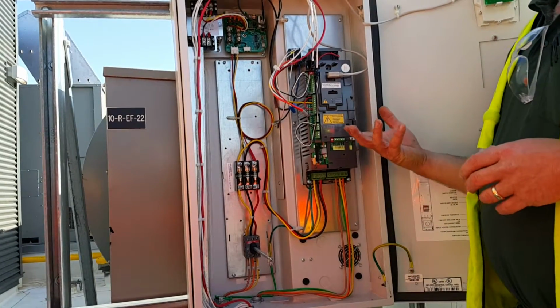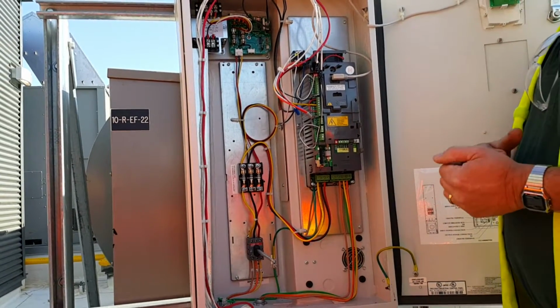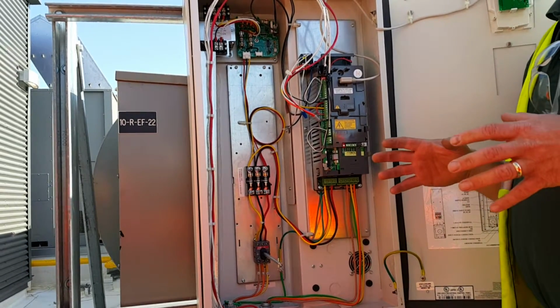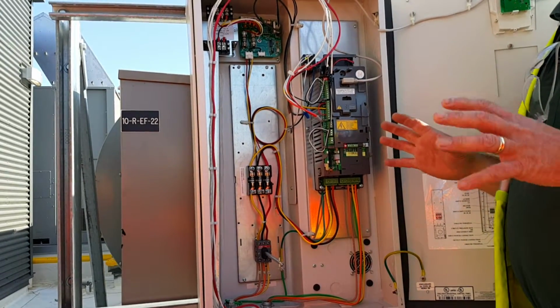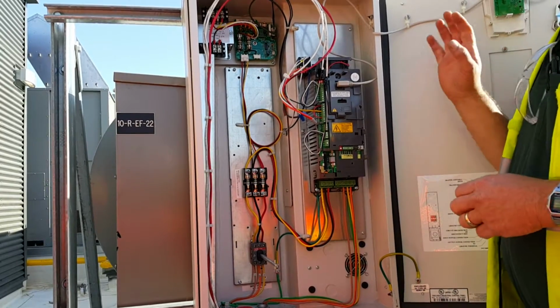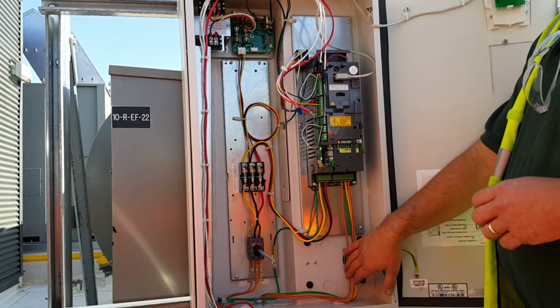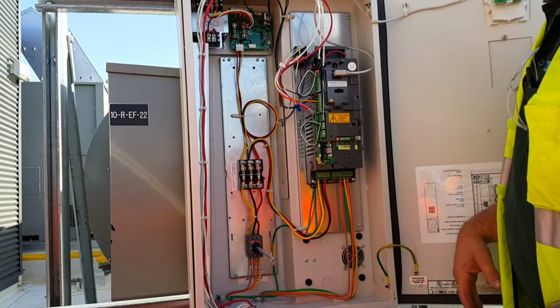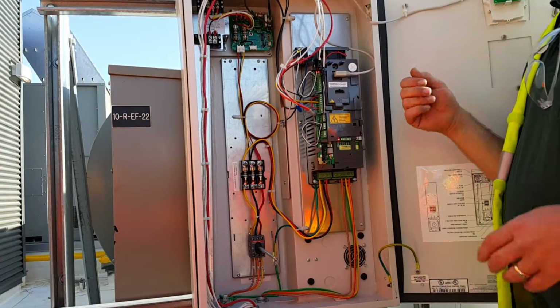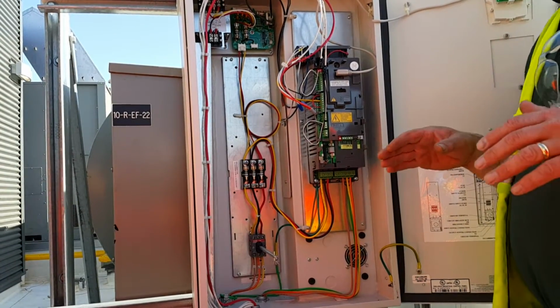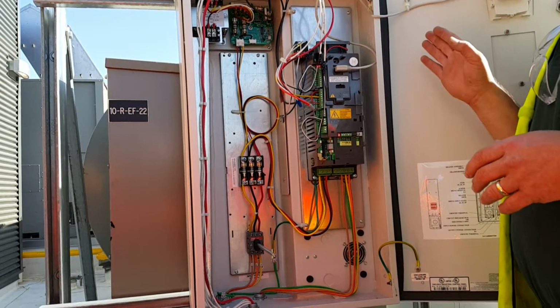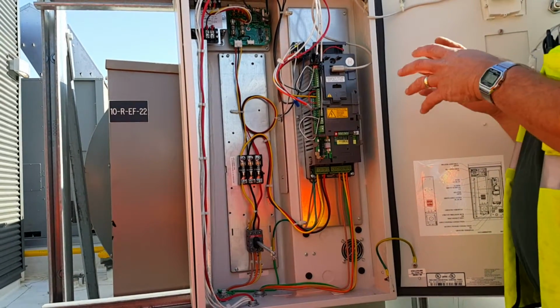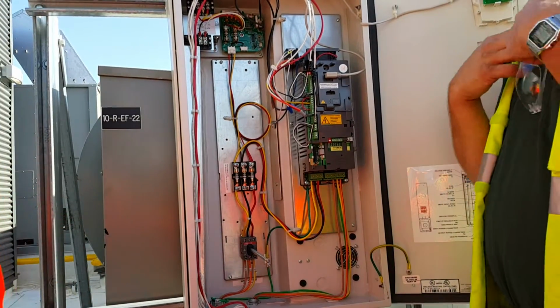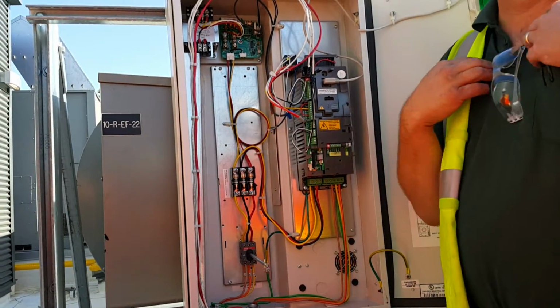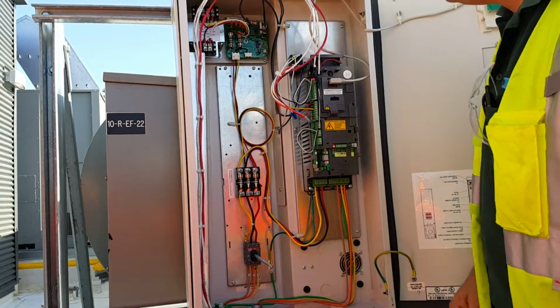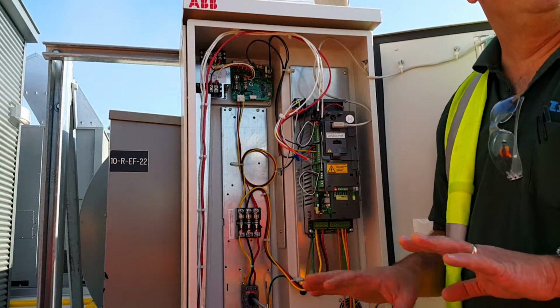Same thing, let's say you get a fault: earth fault, overcurrent fault, short circuit fault, all those faults. For any fault, it's not a bad idea to kill power, remove your motor wires, cap them off, save them off. Turn the drive on, again, run the drive up. If the drive runs, chances are the drive's fine, you've got a motor problem. Just because the fault comes up on the drive doesn't mean the drive's saying, I got a problem, it's saying my motor's got a problem. So you try to do that process of elimination.